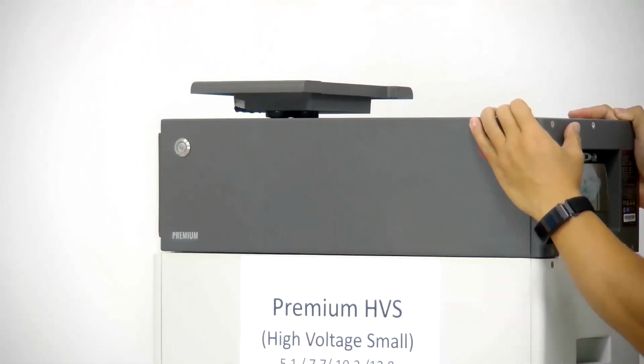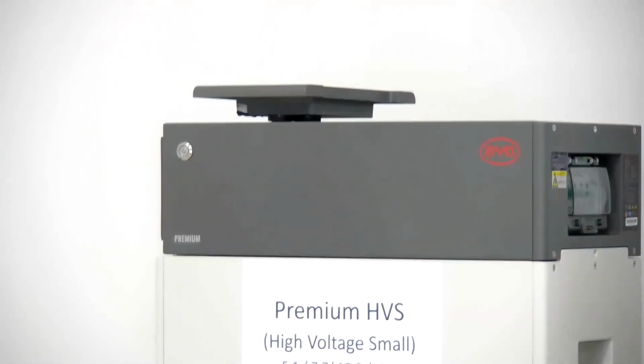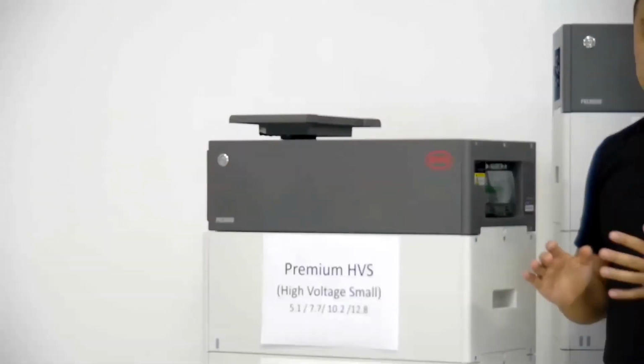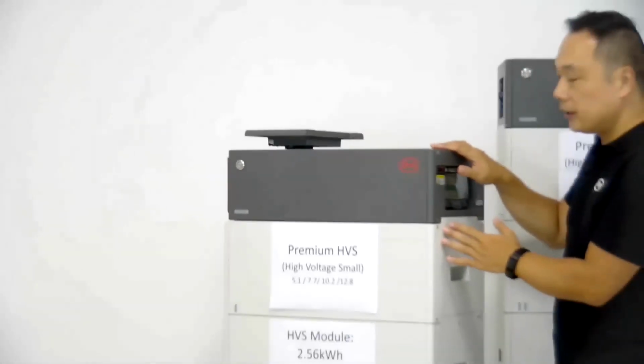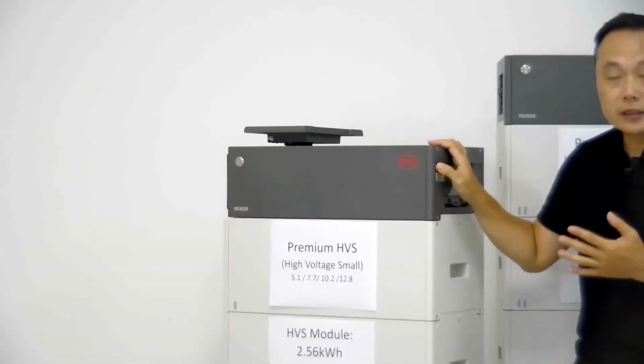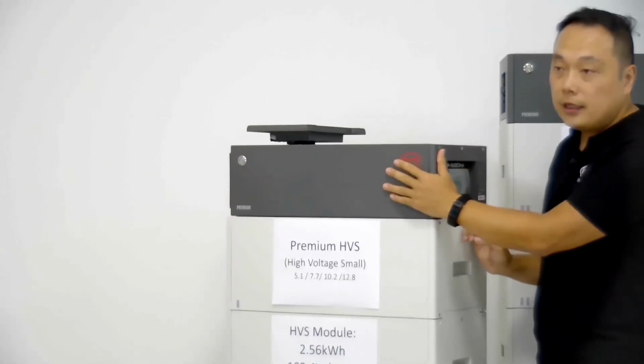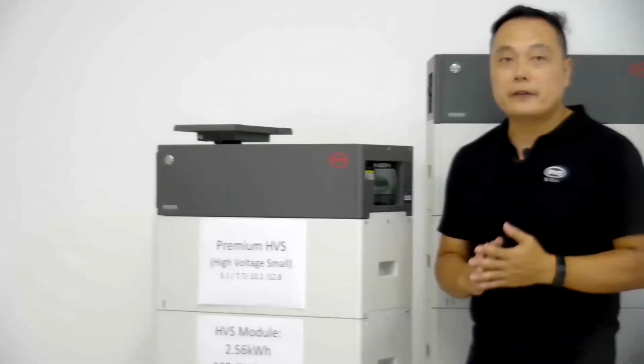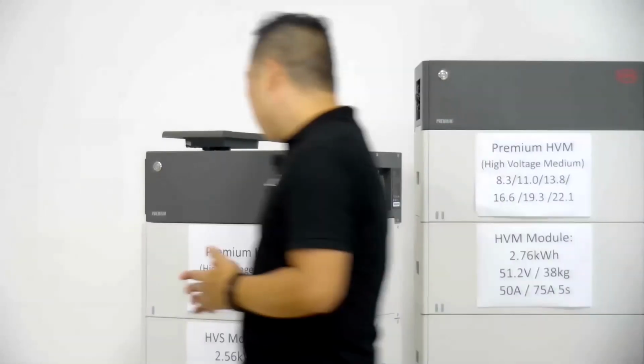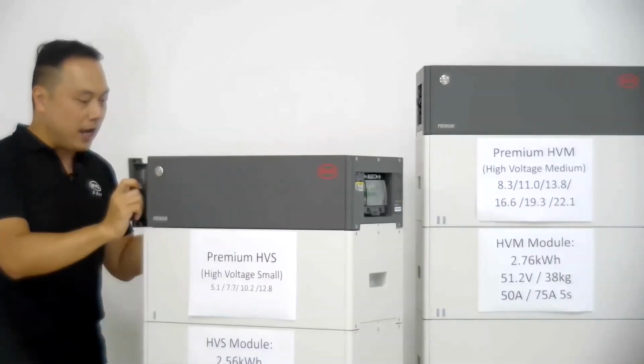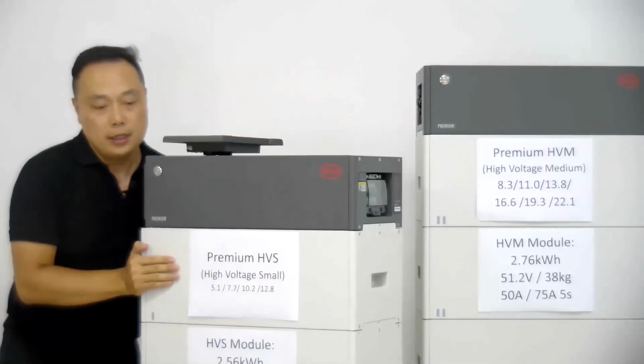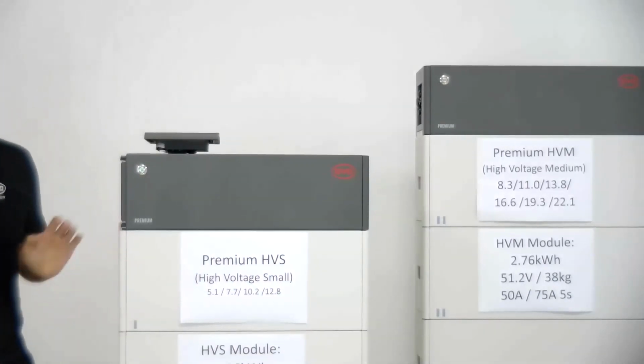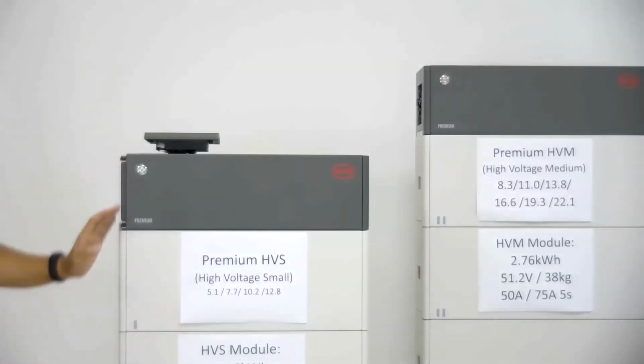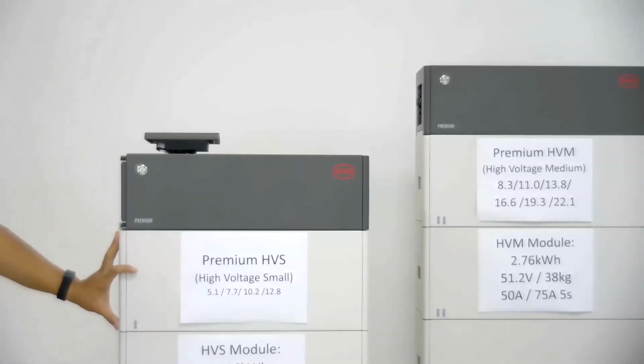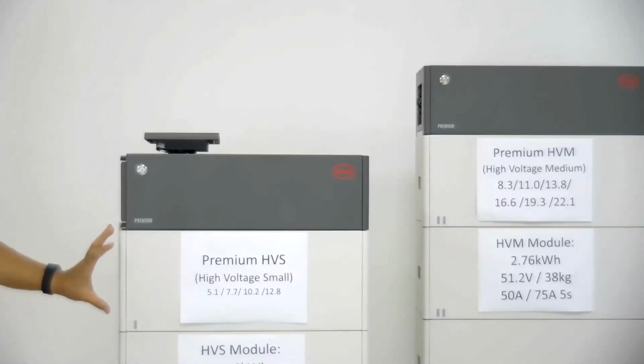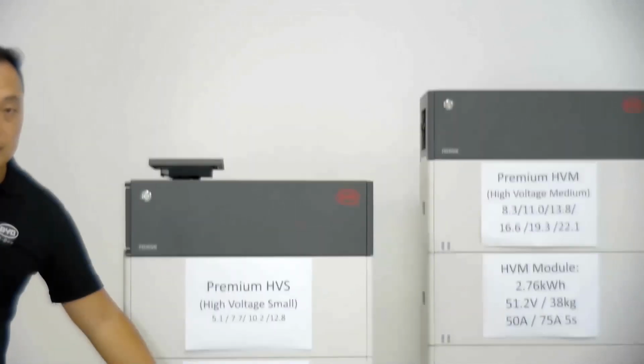Always remember, when turning on, turn on the DC fuse or breaker between the inverter and the battery first, then the battery, and the inverter last. So for high voltage, it's quite simple. Also, if you need to do parallel connection, it obviously requires the same battery numbers in each stack.